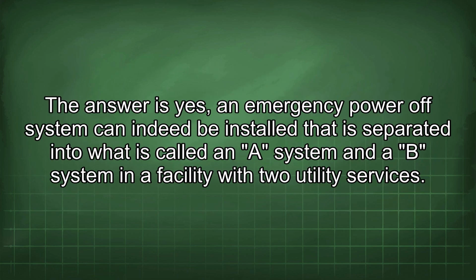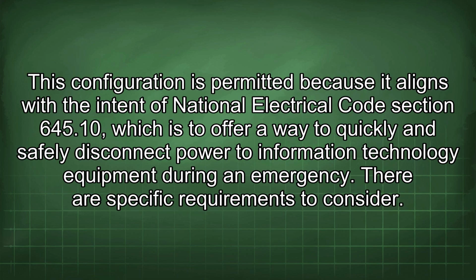The answer is yes. An emergency power off system can indeed be installed that is separated into what is called an A system and a B system in a facility with two utility services. This configuration is permitted because it aligns with the intent of National Electrical Code Section 645.10, which is to offer a way to quickly and safely disconnect power to information technology equipment during an emergency. There are specific requirements to consider.